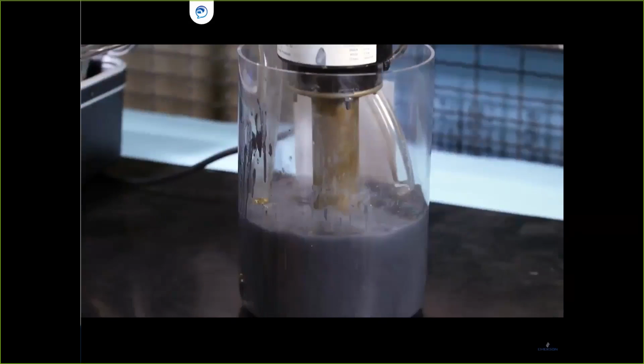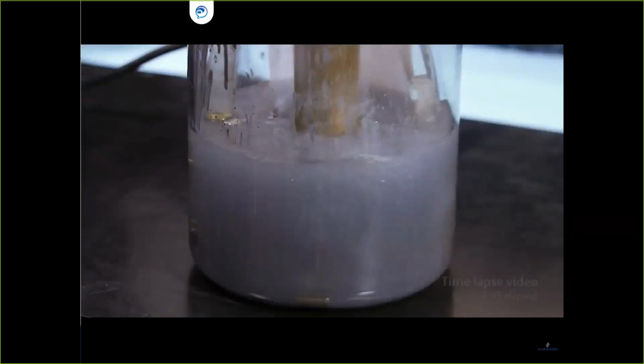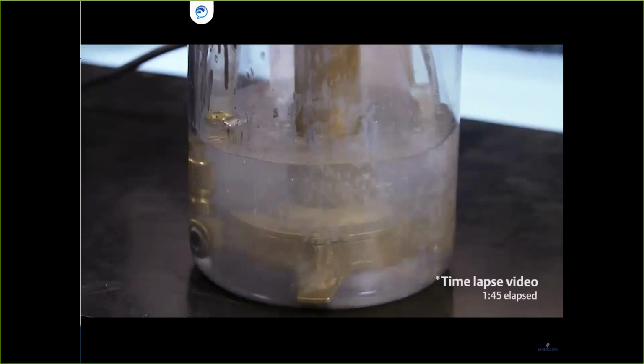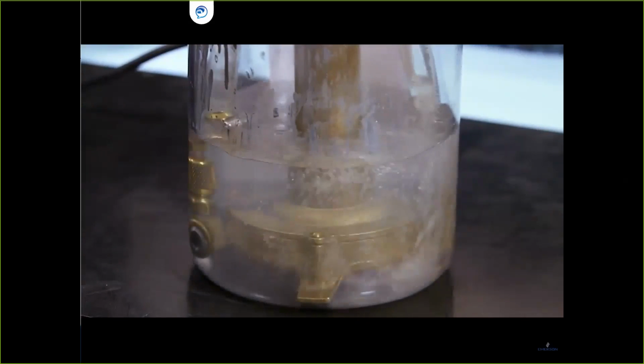Now we add another 5 grams of contaminant. You'll see how quickly the Emerson EK cleans up the system. In about 1 minute and 45 seconds, the EK cleans up not only the contaminant left in the system by the competitor's filter dryer, but also the grit we just added.